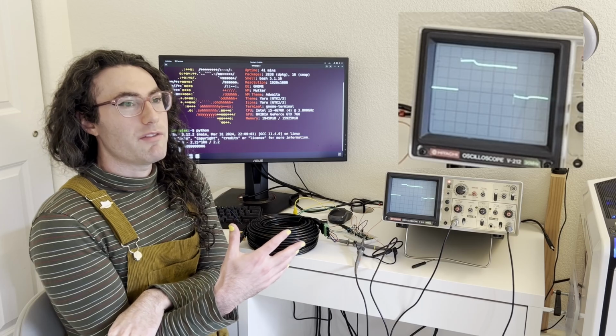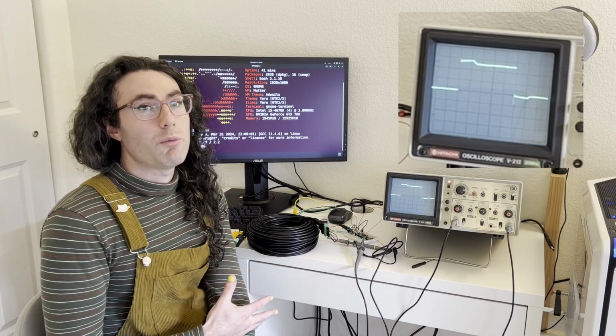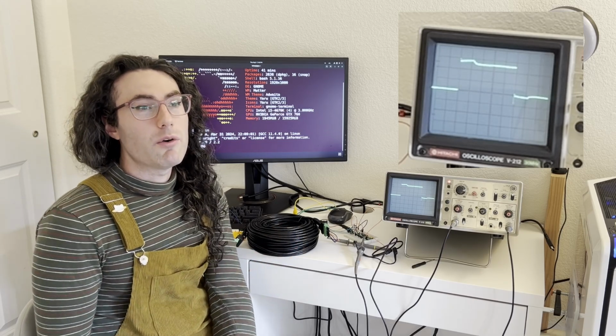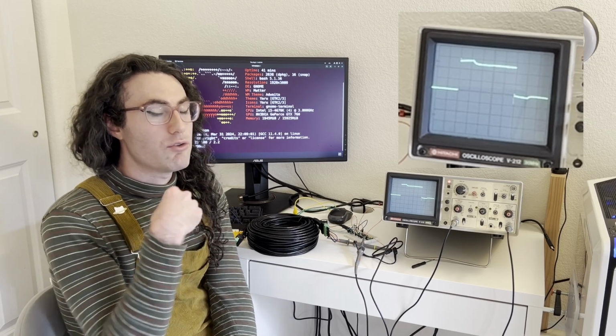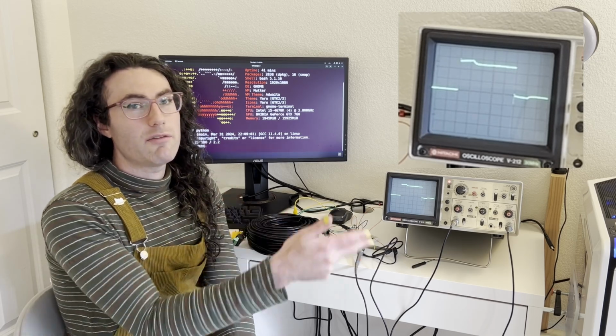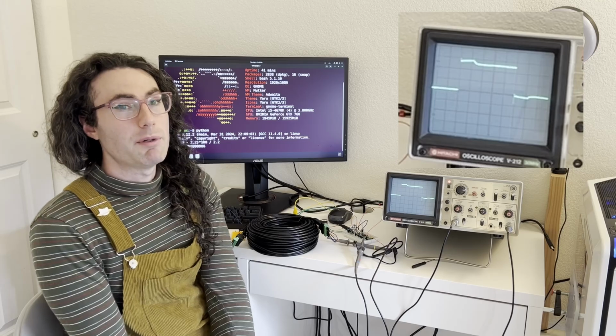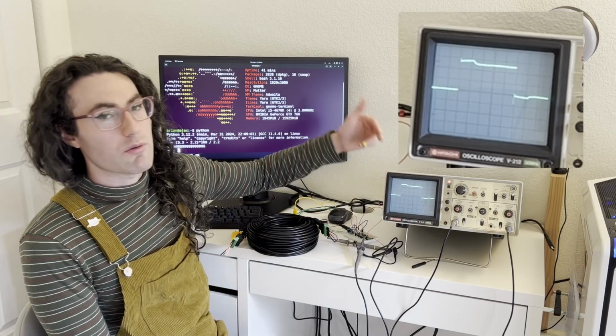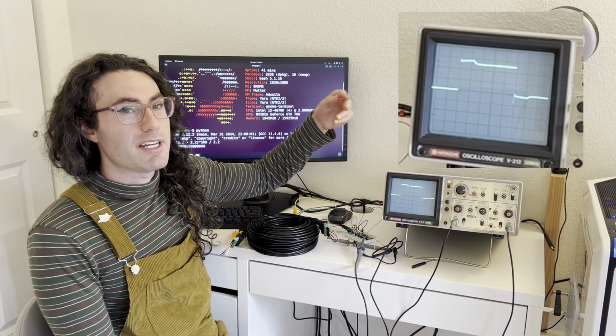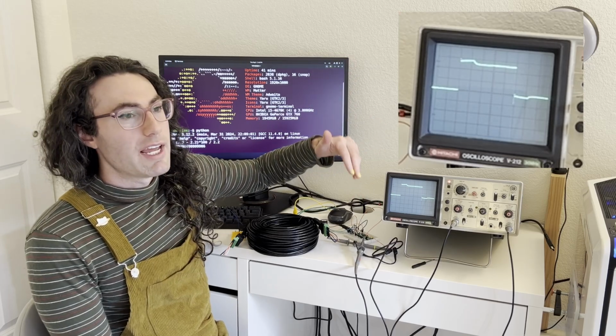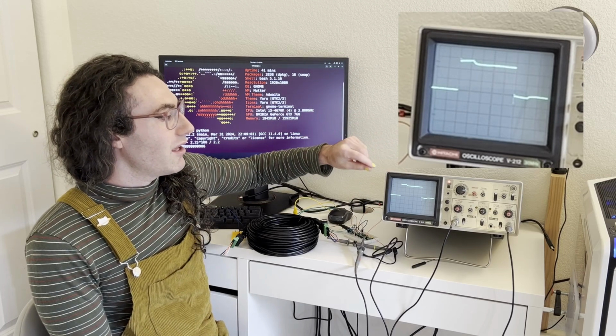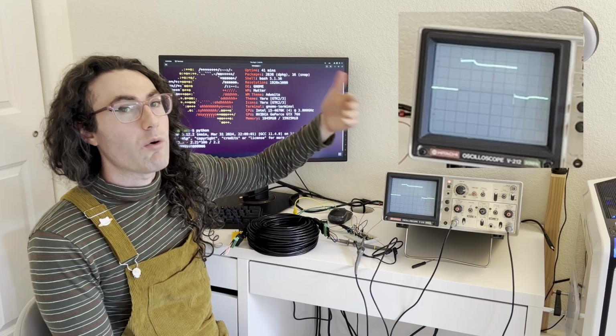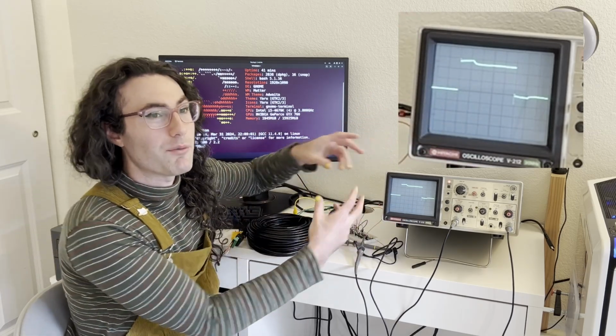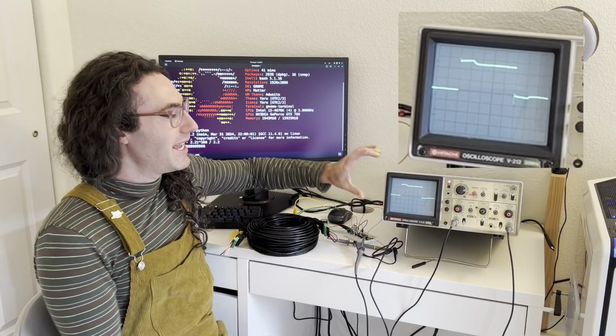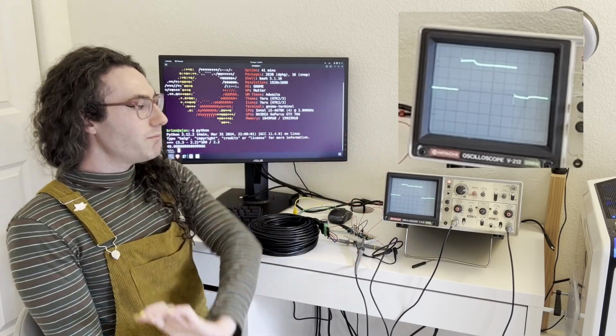But this is one of the features that a digital oscilloscope will have, in that it can run in single mode, where once the trigger gets hit, it will collect data for as many samples as it can take, and then it will stop. With the analog oscilloscope, we can't do that. We have to have the continuous signal going on and off, so that we can look at that moment in time that's getting repeated over and over again. We can't just look at it once and freeze the screen, unless maybe you had a really fast camera and knew exactly when to hit the shutter to take the picture.